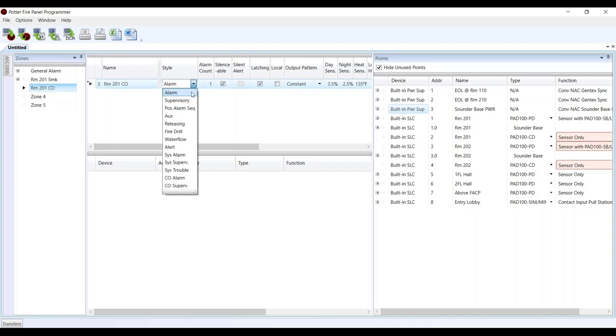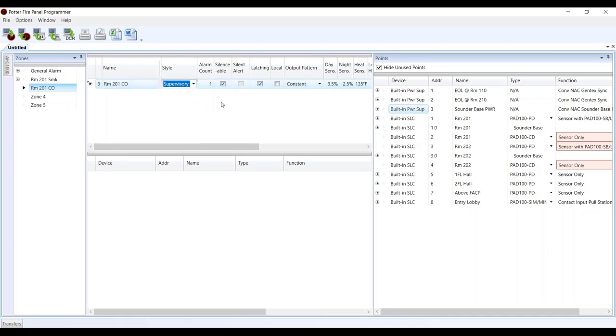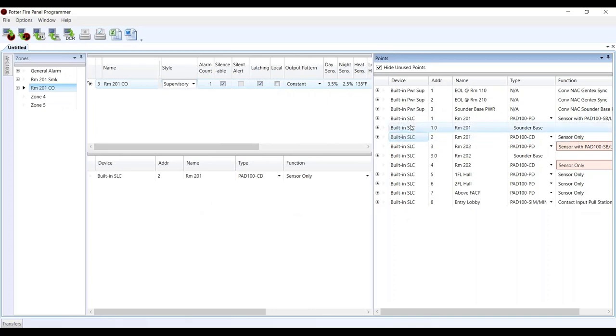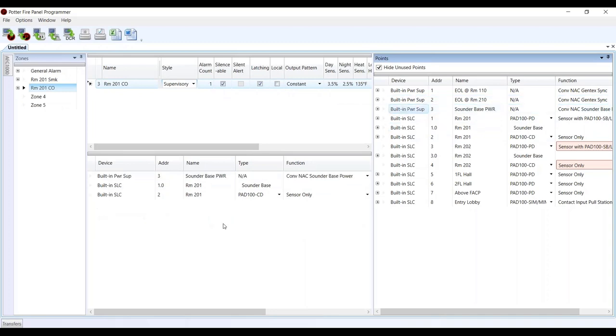Then the sounder base power goes into zone 3, which will be the CO detector for that room. This one's going to be a supervisory style zone, silenceable, latching. We grab the CO detector, the actual sounder base itself, and then the sounder base power. So we're only using one sounder base inside the room — on the smoke detector — and we're just going to funnel those signals through that one sounder base.